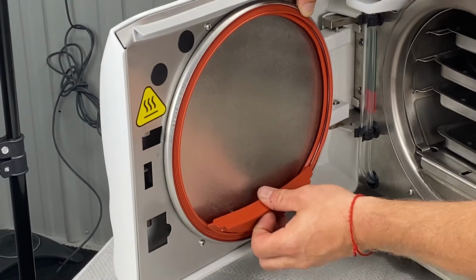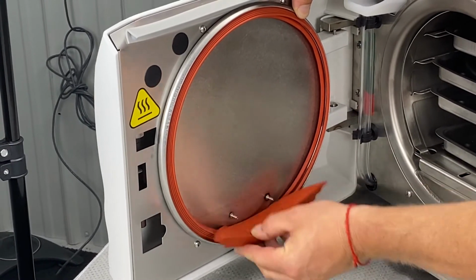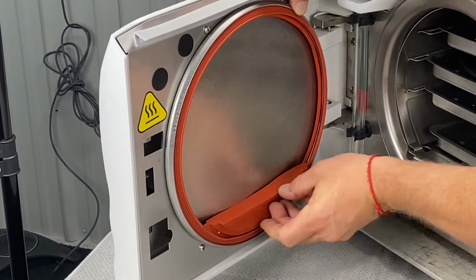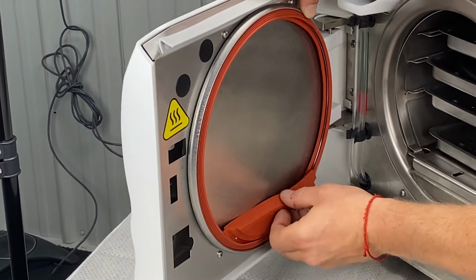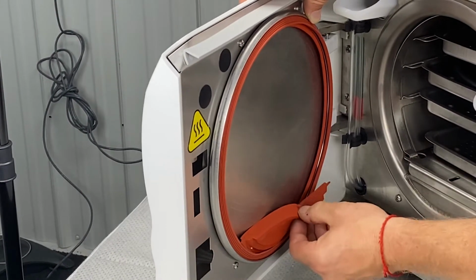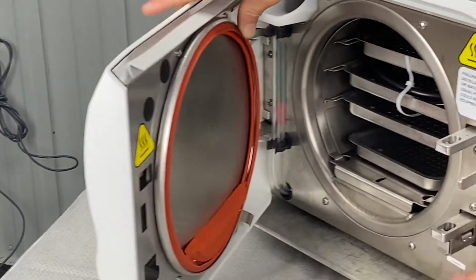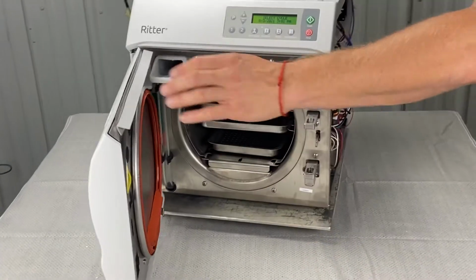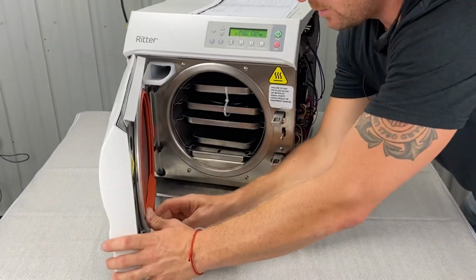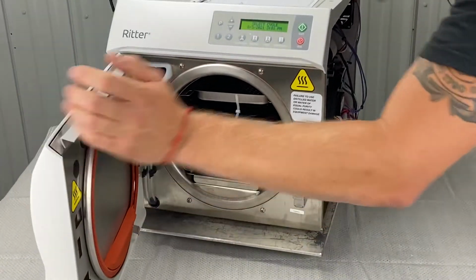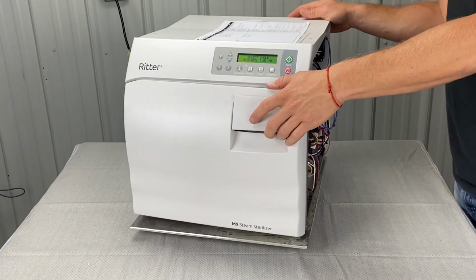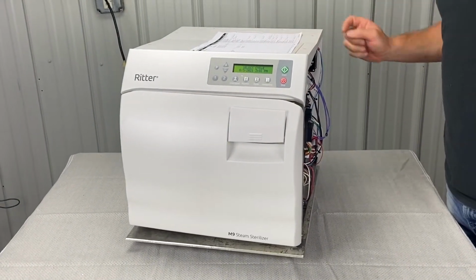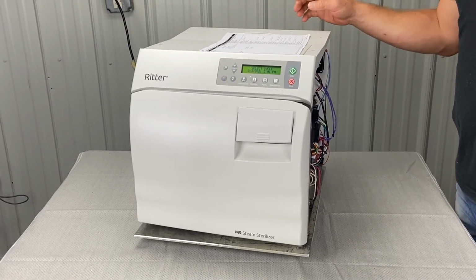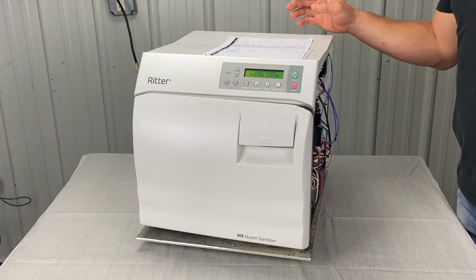So it could be the gaskets, door gasket, dam gasket. Dam gasket lasts a little bit longer than the door gasket. It's just a fatter piece of rubber and just kind of sits down here. Sometimes they'll melt to the chamber. Then you obviously need to replace it. So you're gonna wanna make sure that all the gaskets are seated properly. Worn or damaged gaskets, water leaking around the door. Verify door and dam gaskets are installed properly.